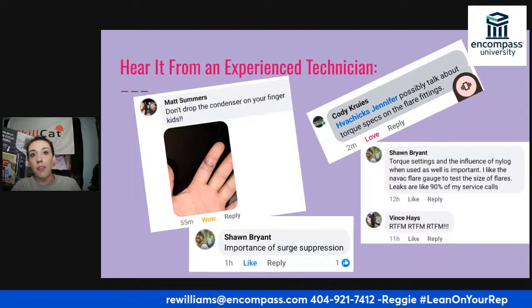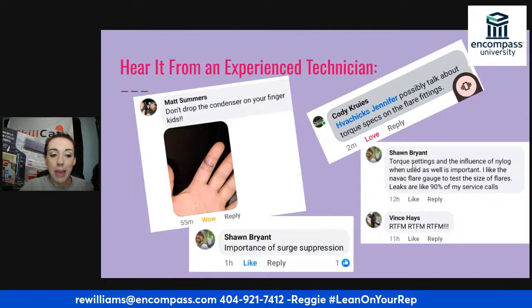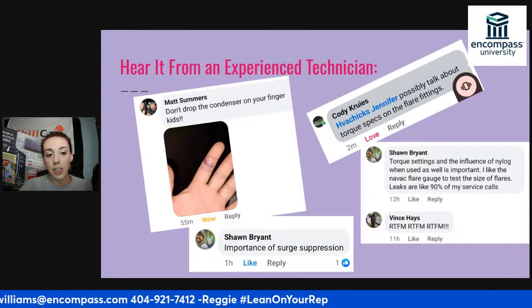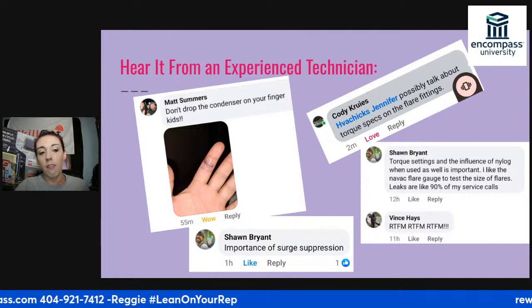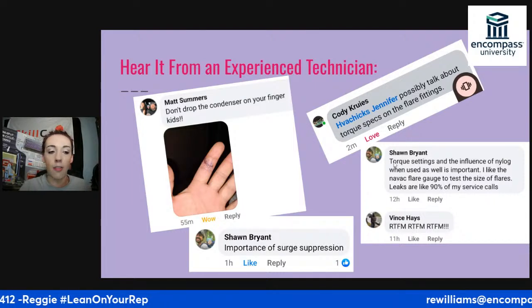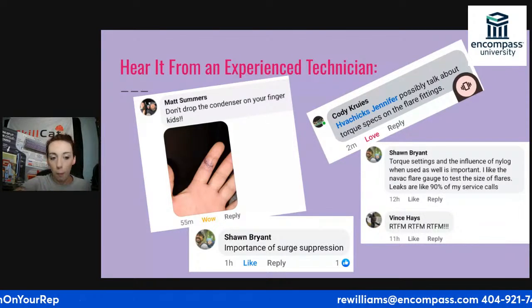And then the other thing is torque. In the manual of every single mini split, you'll have torque settings, what you need to use on a torque wrench for that flare nut, how many pounds of torque you need to stop at.